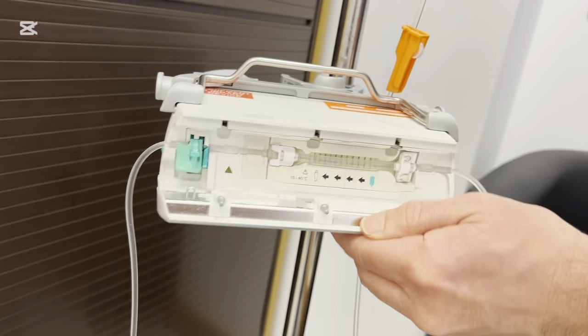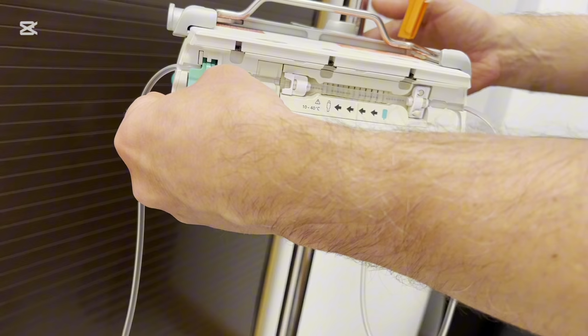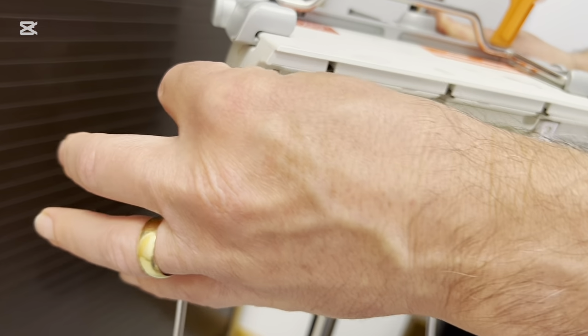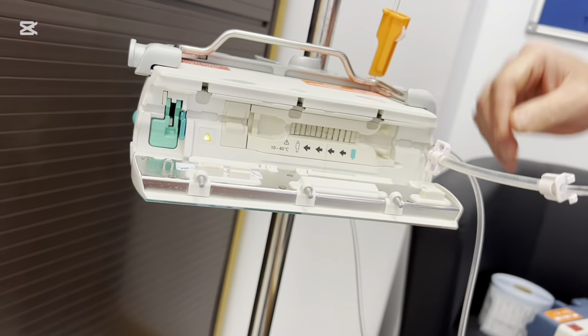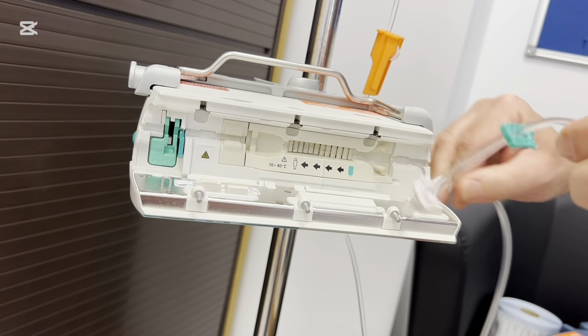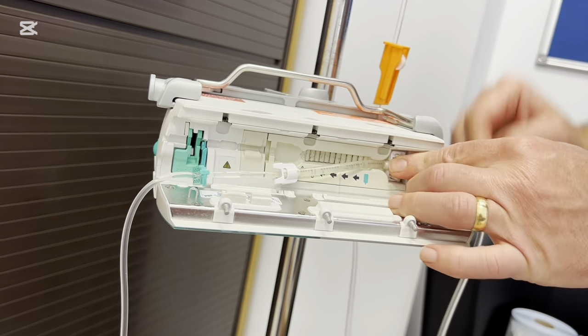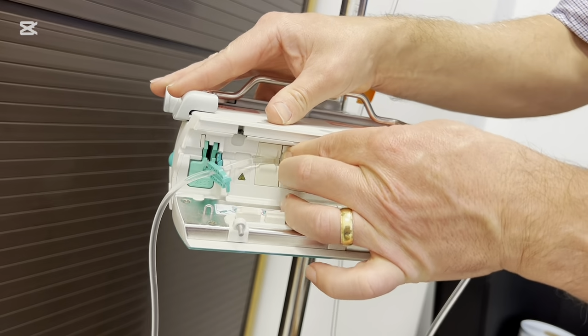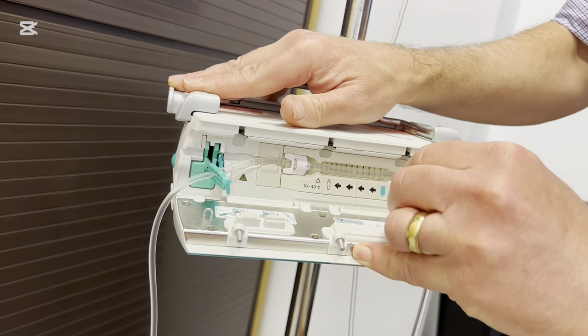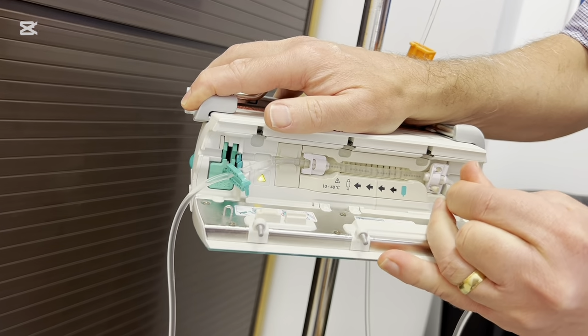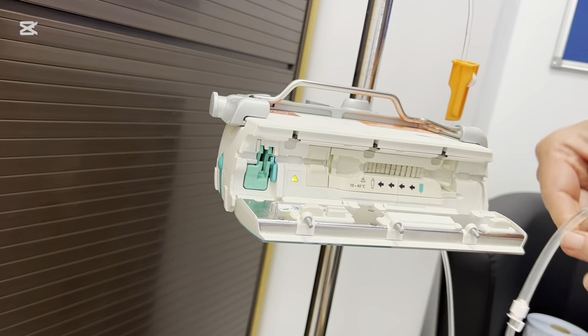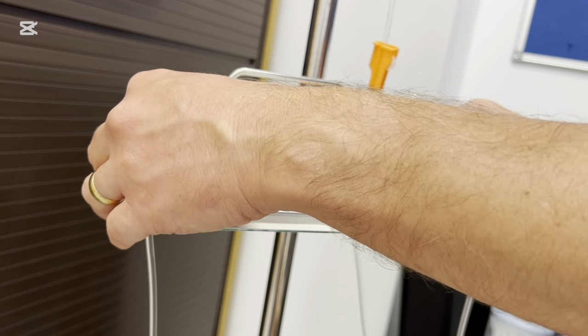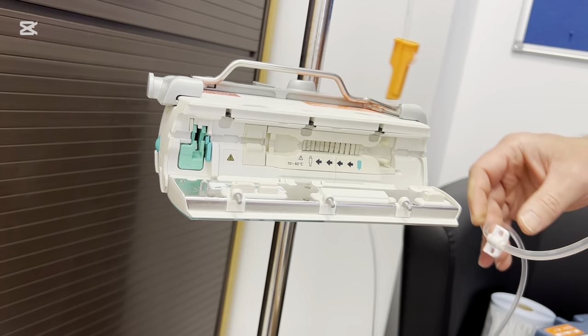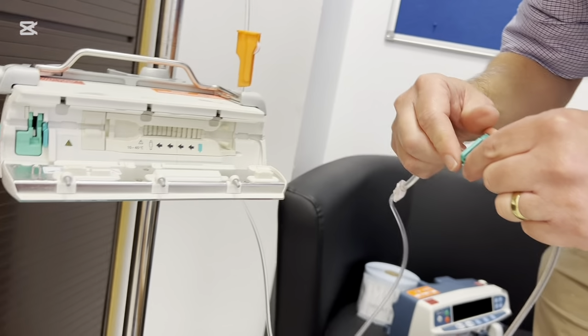Open the door. Now you need to press this to release the clamp and then just pull it out. Make sure that you don't inadvertently pull this pumping segment out. That can be done if you pull the pump out, pull the strip out the other way, and it takes some effort, but you can. Oh, no, you can't. In some of them you can pull it out, but if you follow the correct instructions and just depress the green button and then pull it out this way, you shouldn't run into any problems. When you've done that, this can now just be used as an ordinary gravity set.